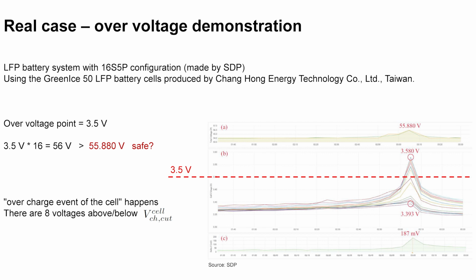The difference among charge-discharge characteristics of battery cells can be observed directly from the voltage difference between the maximum and minimum cell voltages, delta V, as shown in figure C. When the system is near full charge state, delta V gradually increases from 30 to 187 millivolts, indicating that the voltages in various parallel connections gradually deviate, reaching a maximum deviation at delta V equals 187 millivolts.